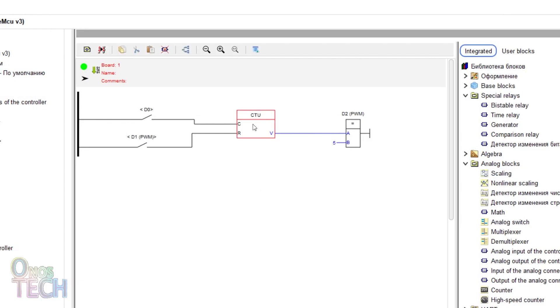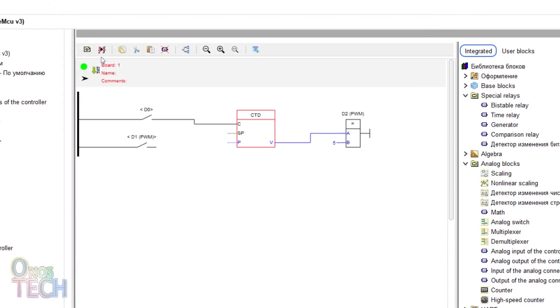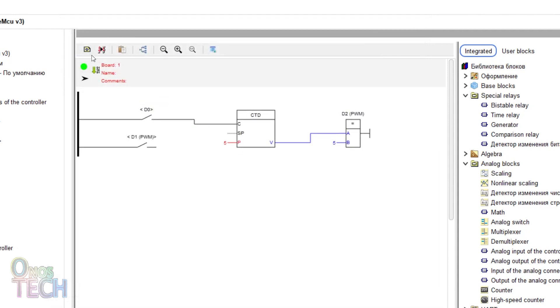Now, set the counter to the down counter type and enable the preset and input type. Left click on the counter P input and enter integer 5. Connect the D1 input contacts to the SP input of the counter.